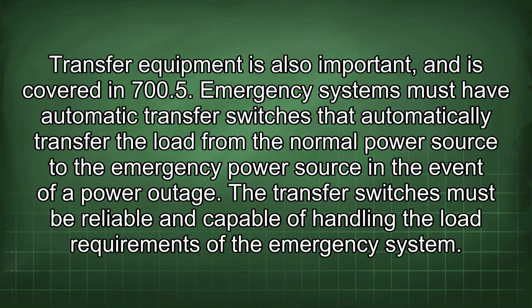Transfer equipment is also important and is covered in 700.5. Emergency systems must have automatic transfer switches that automatically transfer the load from the normal power source to the emergency power source in the event of a power outage. The transfer switches must be reliable and capable of handling the load requirements of the emergency system.